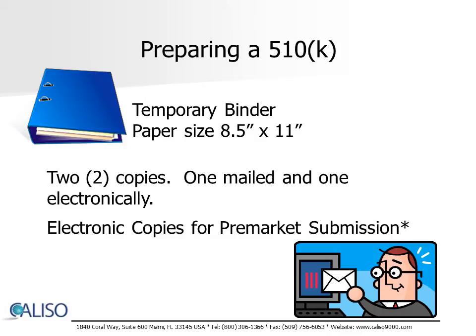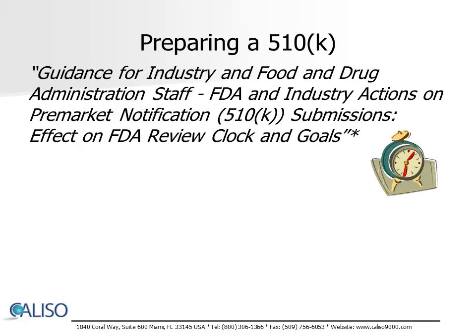Details of how to submit electronically can be found in the link Electronic Copies for Pre-Market Submission. Please note that the FDA does not return the 510(k) once they've completed their review. There is a time frame that the FDA follows in reviewing and responding to your submission. Please review Guidance for Industry and Food and Drug Administration Staff, FDA and Industry Actions on Pre-Market Notification Submissions, Effect on FDA Review Clock and Goals.